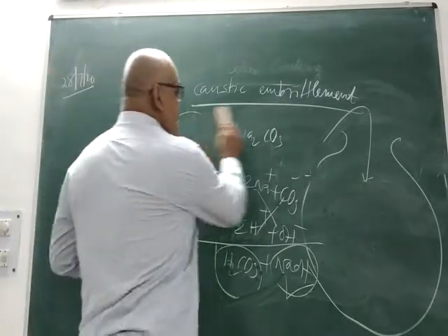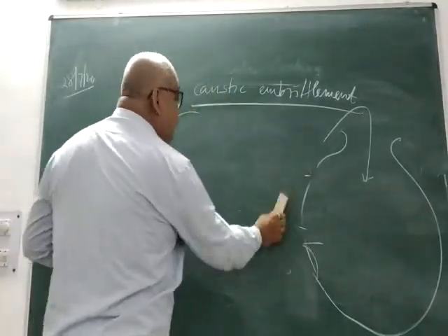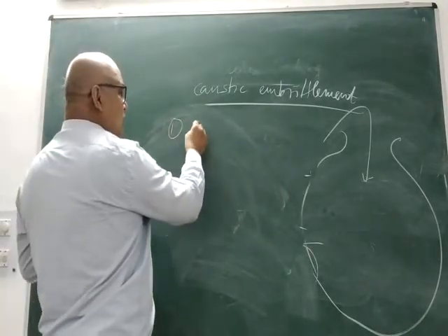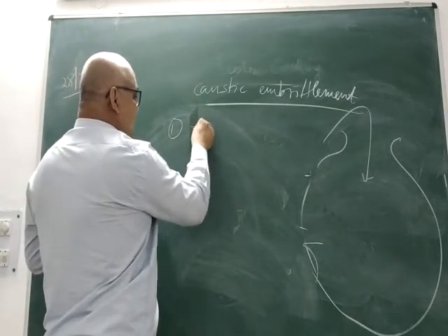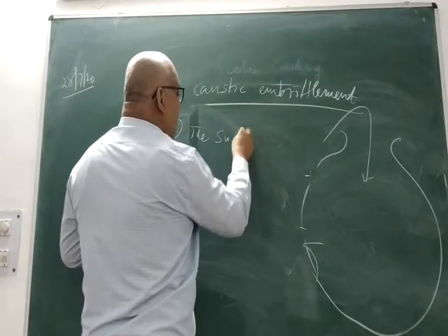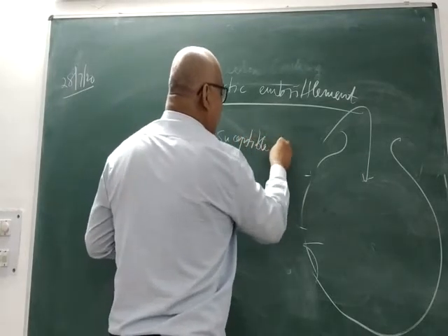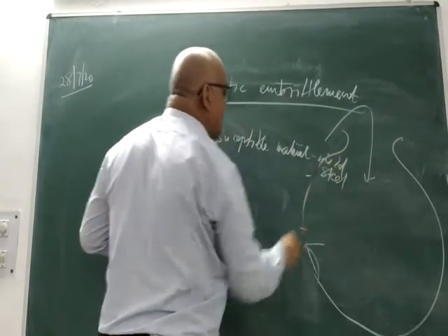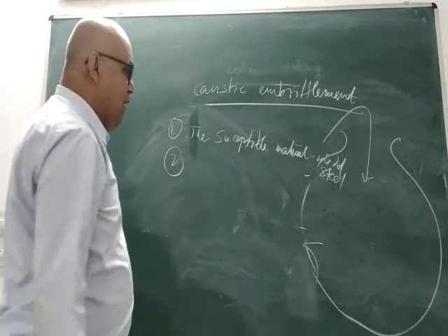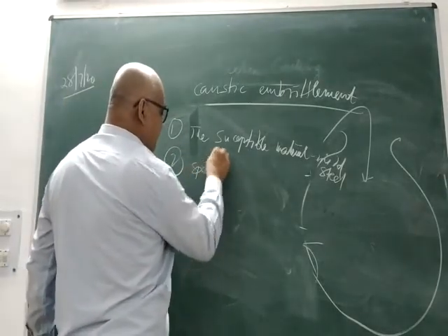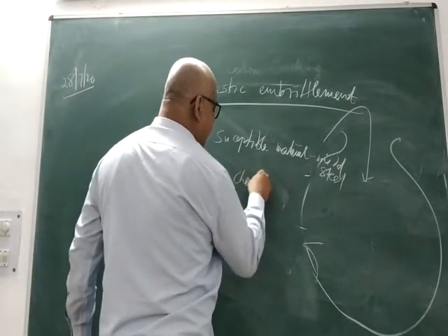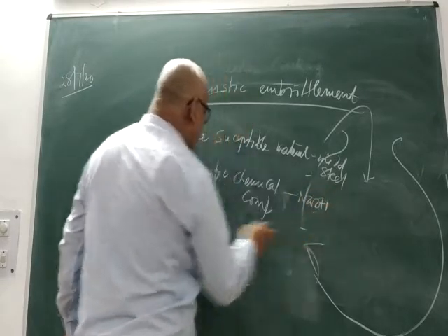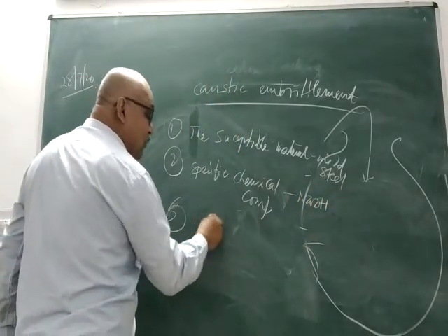Now, as I have told you, here also there are three essential conditions. Number one is the susceptible material, that is your mild steel or carbon steel. Number two will be your specific chemical component, this is your sodium hydroxide. And number three will be your residual stress.